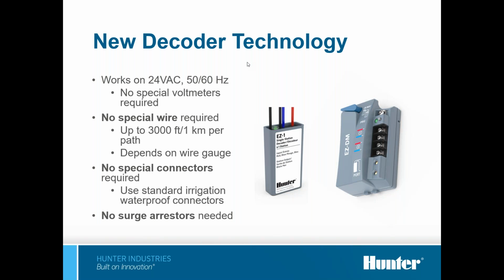There's no special wire required. You can use existing wires as long as they're good. You can go up to 3,000 feet if you have the proper gauge wire. Now, being AC volts, you have to follow AC volt wire laws. Typically, most systems are done with 14 gauge. 14 gauge is about 2,290 feet. So it really does depend on your wire gauge, how far you can go, and how many you're turning on at the same time.